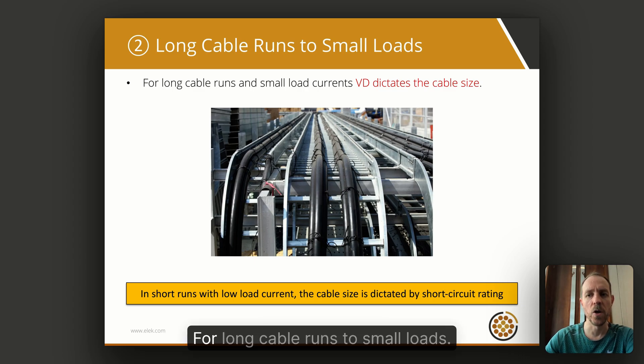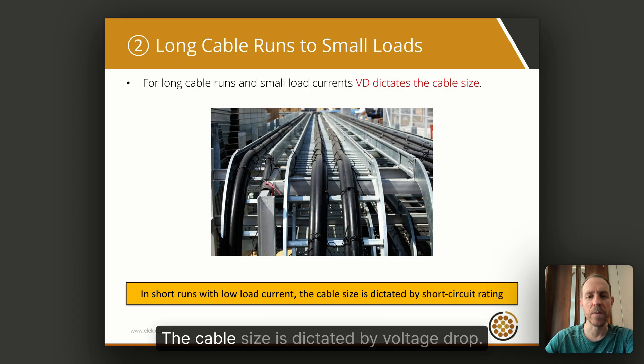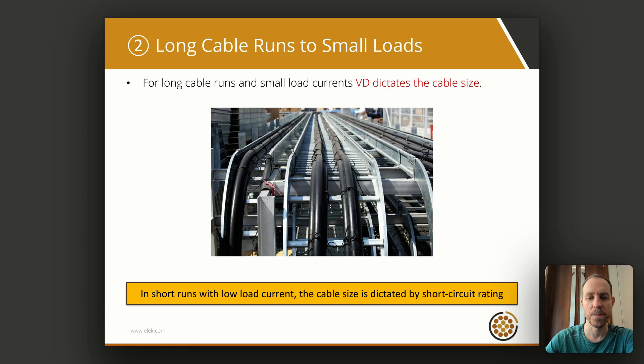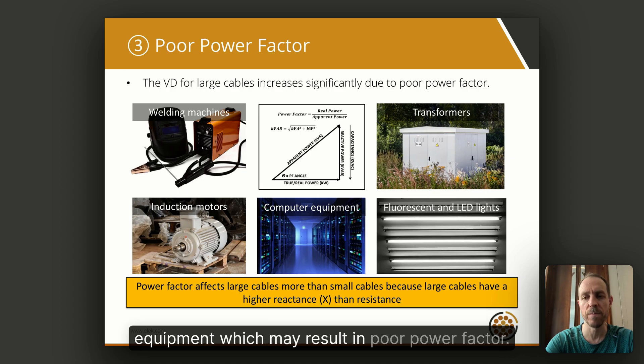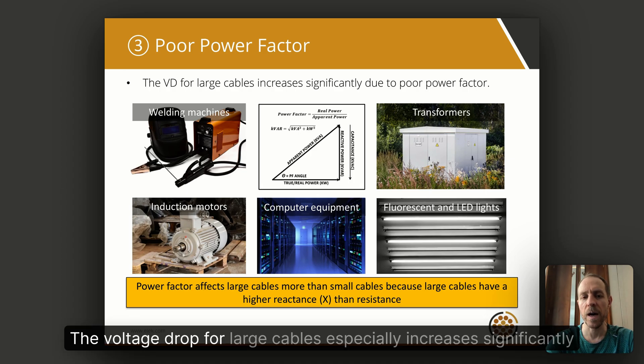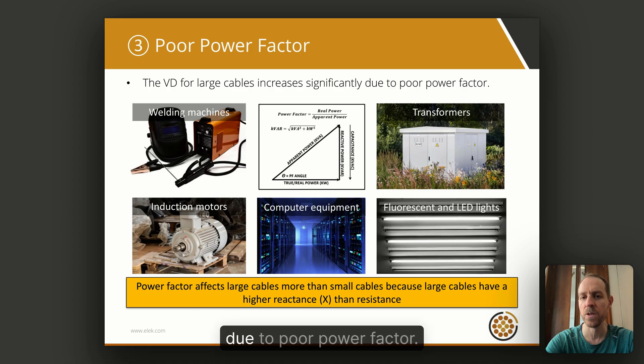Tip number two: for long cable runs to small loads, the cable size is dictated by voltage drop. Tip number three: poor power factor. Here are some images of equipment which may result in poor power factor. The voltage drop for large cables especially increases significantly due to poor power factor.